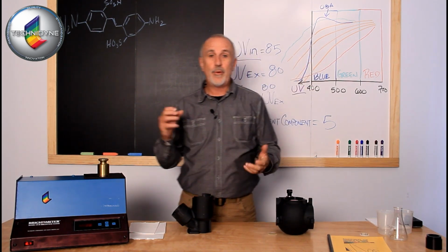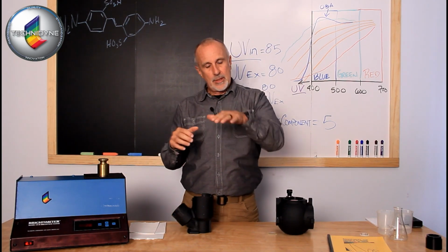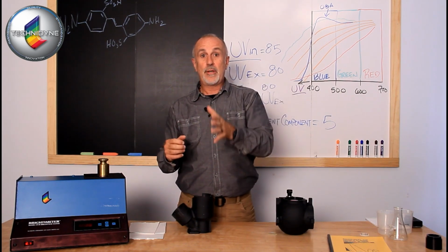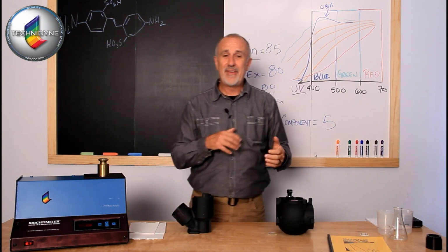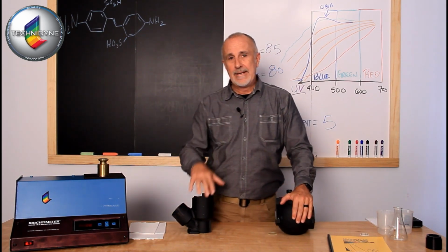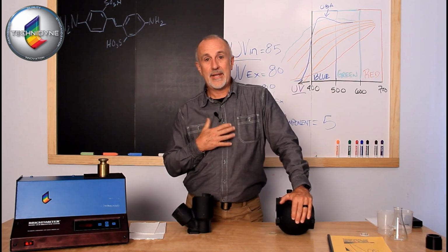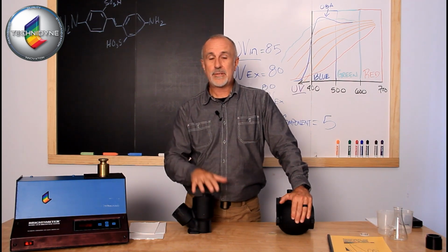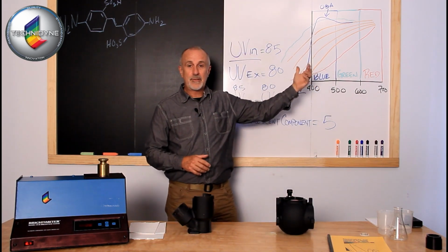Now, if you're using a pulse xenon flash lamp, through the primary calibration of that instrument, it'll start pulling that trim filter out a bit more, so you can get more light into that. But at some point, it's going to be absorbing enough of that UV energy that it's not going to measure it accurately. So part of any good preventive maintenance program, part of our preventive maintenance program here at Technidyne, is to do an evaluation of those spheres whenever we go in and look at them, or we service an instrument, to make sure those spheres have not yellowed sufficiently that they're affecting this.